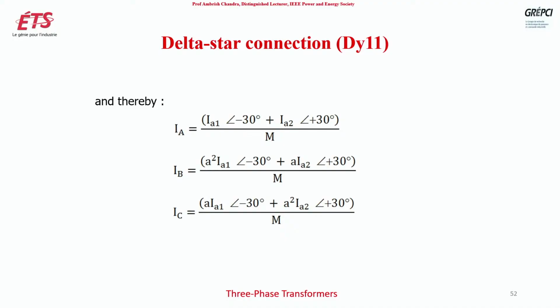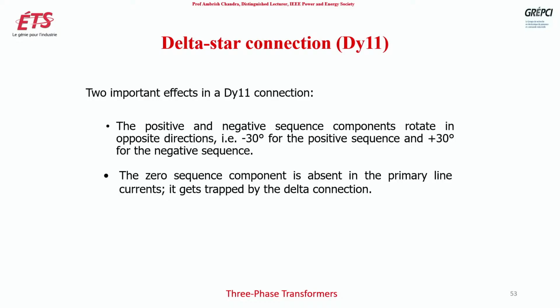So two important effects in DY11. Positive sequence and negative sequence components rotate in opposite directions. Minus 30 for positive sequence, seventh harmonic, plus 30 degree for the negative sequence, fifth harmonic. Zero sequence current is absent in the primary line of the currents. You see, in IA, this is the primary side current which is going to the line of the primary side. There is no zero sequence currents. They get trapped by the delta connection.